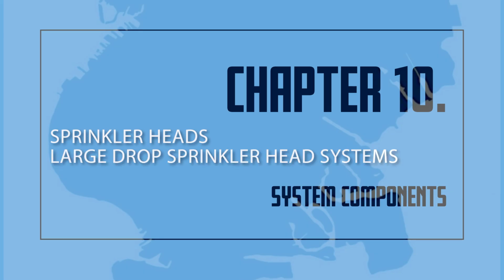Systems using large drop sprinkler heads. Large drop sprinkler heads are special sprinklers designed to discharge large drops of water from the head. These sprinkler heads are used to break through the strong updrafts of high-challenge fires. In places where the temperature is normally high, such as boilers, ovens, and drying rooms, a sprinkler head with a higher temperature rating must be used. This is to make sure that the sprinkler head does not discharge water at the wrong time. If heads with a high temperature rating are used in an ordinary room, like an office, an apartment, and store, the value of the sprinkler protection is greatly reduced. This is because the temperature will have to increase much higher for the sprinkler heads to open.